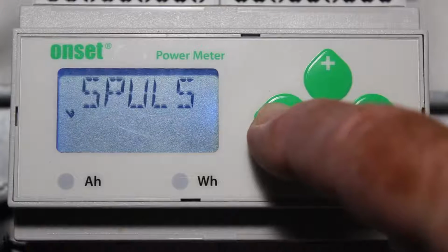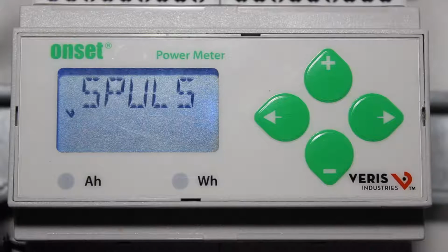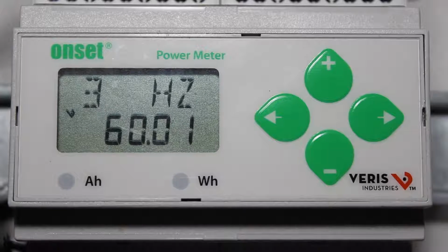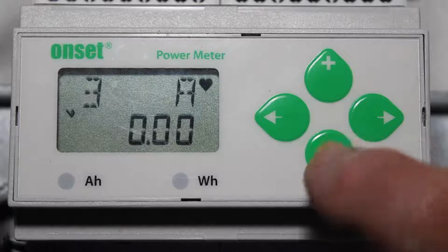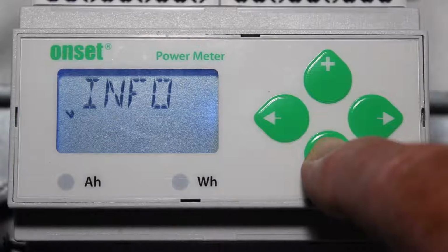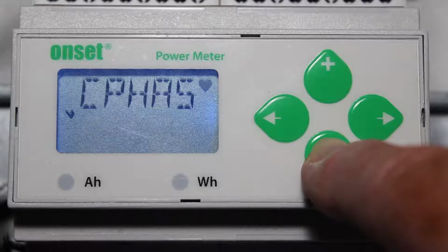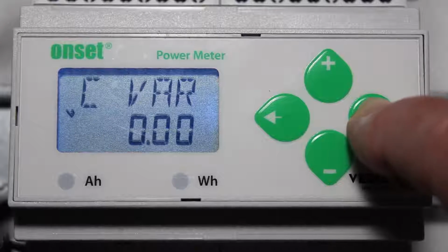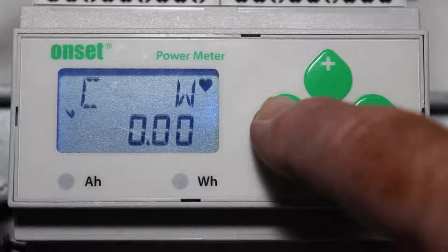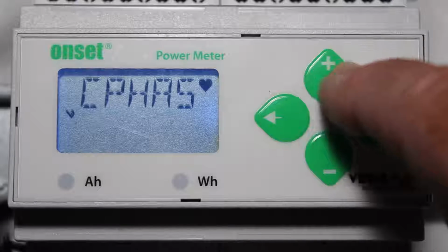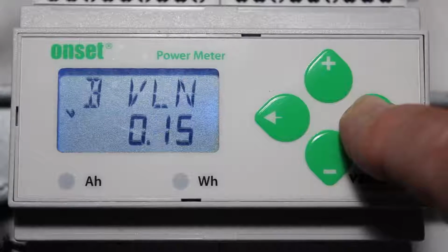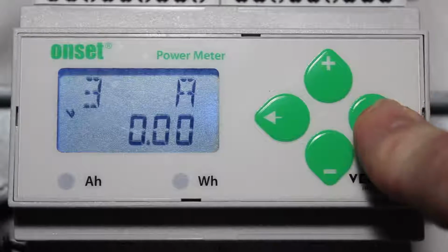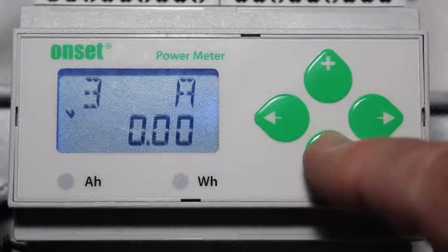So we're going to get ourselves out again. We finished our configuration, and we can see it's scrolling through those measurements for all 3 phases. That's what it says 3 there. If we want to see what each phase is reading, we arrow down again through the menus, and we see C phase. If we right click, see amperage, voltage line to neutral, watts, VAR, VA. Back out of that. Down, there's B phase, all the different variables. Down, and then if we say 3 phase, we can see what the total is for each.